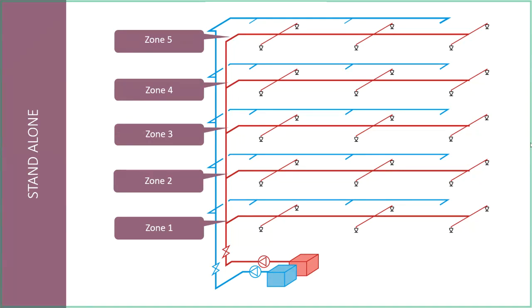Because for us, sprinklers are really important, and we don't like to be relying on other people's work, essentially. With a standalone system, we've got all the water we need in a tank completely separately. It's secure. Nothing can steal the water from us. It's there, it's ready. We don't have to rely on the town main because all the water we need is already in storage. We have our own fire pump, which we test, and again we know that's going to work. It's specifically designed for the job, so the power of the pump has been calculated to meet the demand and the design of the system. We've got our own valves, our own riser pipes. Everything is completely separate, which is, I would suggest, the way that the majority of the automatic fire sprinkler industry would ideally like it.